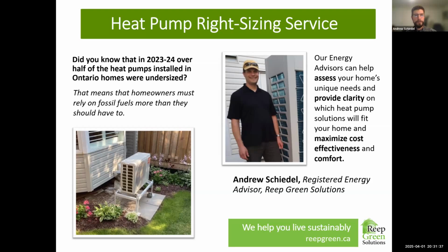So we can say, okay, this looks like you have this much—if you have 100 amps and it comes out at 70 amps, you've got 30 amps available, that kind of thing. We also take a quick look at the panel to see if there's any space available or something that might become available. For example, you might have a breaker for an air conditioner—if you're putting in a heat pump instead, that becomes available.